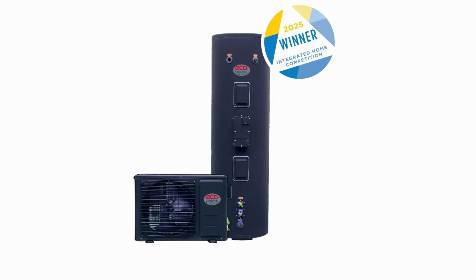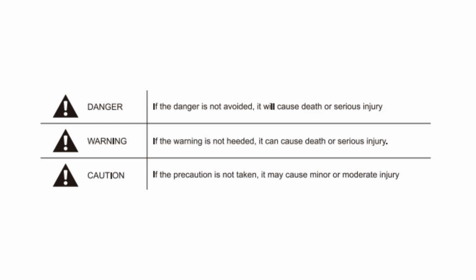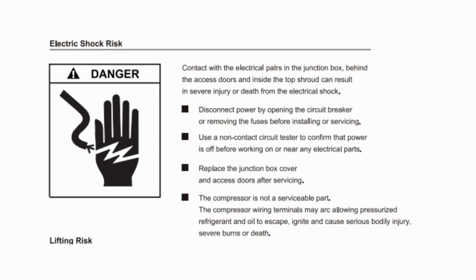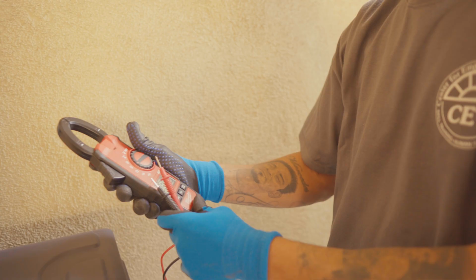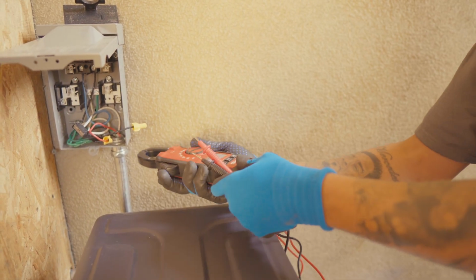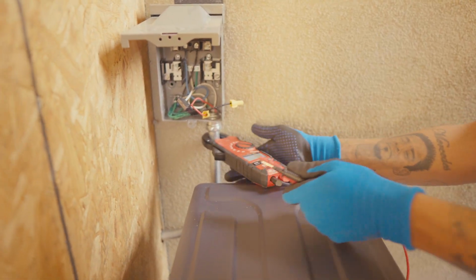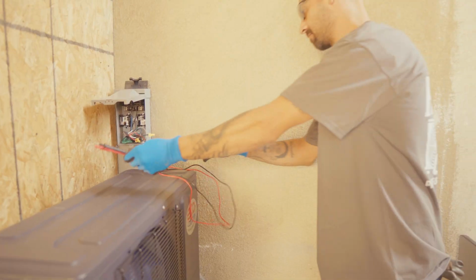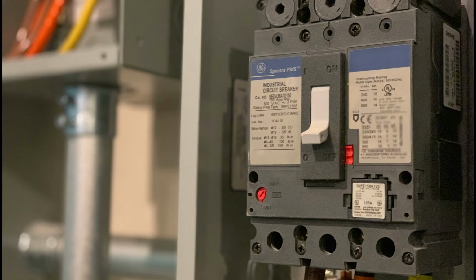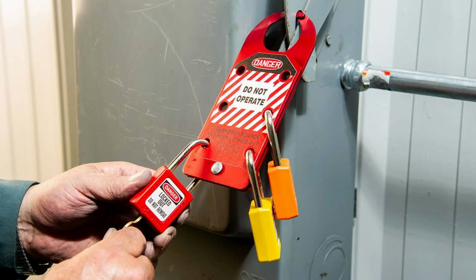When installing this unit, always refer to the manual and pay attention to these symbols, as they contain important information about potential safety risks. Some safety risks are as follows. Electric shock risk. Contact with electrical components in the junction box, behind the access doors, or inside the top shroud can cause severe injury or death. Always disconnect power at the circuit breaker, and verify that it is off before performing any work. Keep the junction box closed at all times when it is not being worked on.